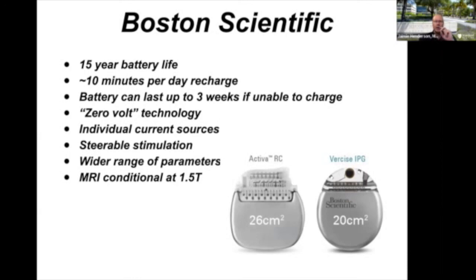And you can also steer it. The current generation of lead that I use lets you steer the current in various different directions in order to avoid some of the potential side effects. There's a wider range of parameters. You can do all sorts of fancy things like have different frequencies for different parts of the lead. So at the higher part, you could have a high frequency. The lower part, you could have a low frequency. So it's got all sorts of fancy features that, if we want to try to get creative with our programming, we can do so. And it is MRI conditional, meaning that you can have a 1.5 Tesla MRI scan under certain circumstances.